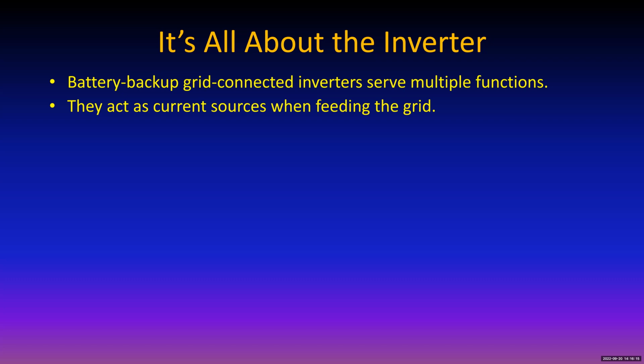The nice thing about having current sources for inverters is that they can be synchronized by the waveform of the utility voltage. These current sources are measuring the frequency and the amplitude of the utility voltage, and as soon as they find that the voltage is nice and stable, they click on right along with the phase of that voltage, unless the utility says, we would like you to help us correct some power factor. So we are going to adjust the output of your inverter so it will look more like a capacitor, to correct some of the inductive current in our line and stabilize it a bit.